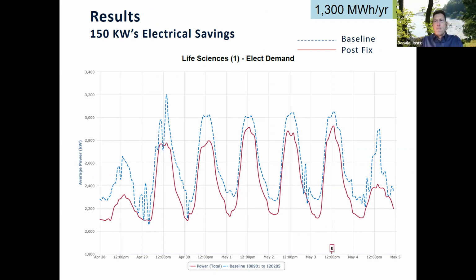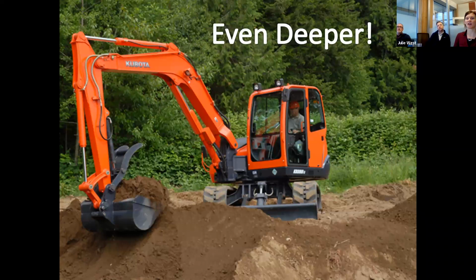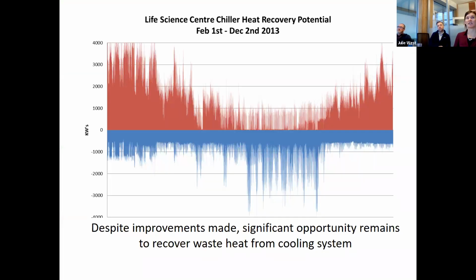So that was our department scratching the surface in 2010 to 2013. And then we started really getting a better understanding of how the building operated through those initial measures and gaining more confidence in our ability to change how the systems operate. So digging even deeper into this building, we had a look at the heat recovery potential in the building. So this is a graph of the heating load in the building in red, and then the cooling load in the building in blue. And so despite the improvements made to date, we found there was still a significant opportunity to recover waste heat from the cooling system.